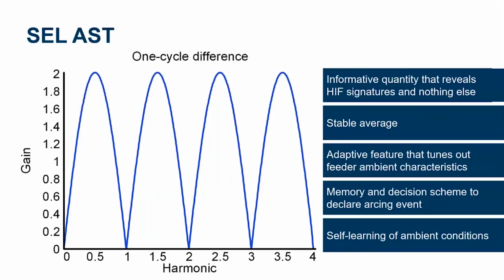Now, one thing that you'll notice here that's very interesting is we're filtering out DC, and we're filtering out all of our integer harmonics. We're looking for the stuff between integer harmonics, so the interharmonic current. And we're summing all of this together for all of these samples over a cycle in order to get what we're calling an interharmonic energy, essentially, of that current. We're going to take this value, trend it, and use that to establish a stable average for the power system.